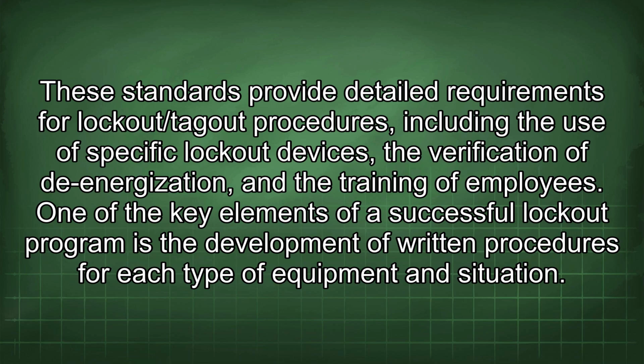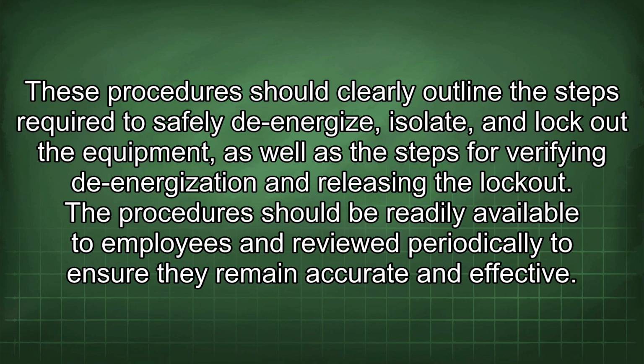the training of employees. One of the key elements of a successful lockout program is the development of written procedures for each type of equipment and situation. These procedures should clearly outline the steps required to safely de-energize, isolate, and lock out the equipment, as well as the steps for verifying de-energization and releasing the lockout. The procedures should be readily available to employees and reviewed periodically to ensure they remain accurate and effective.